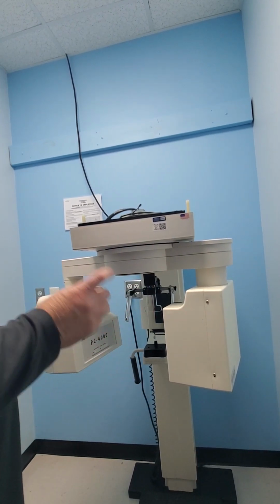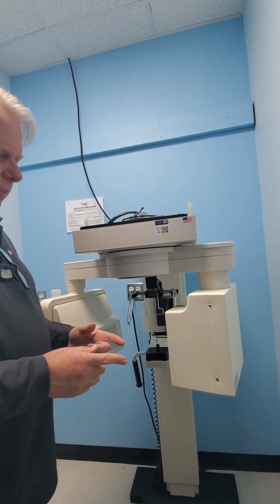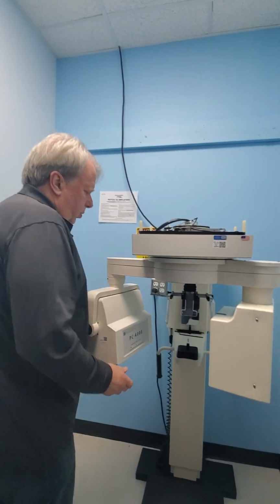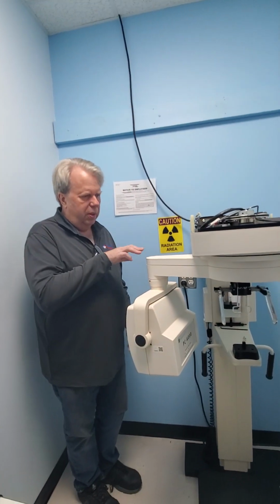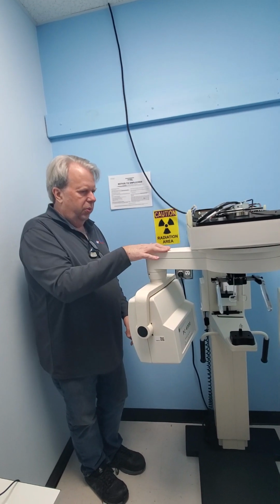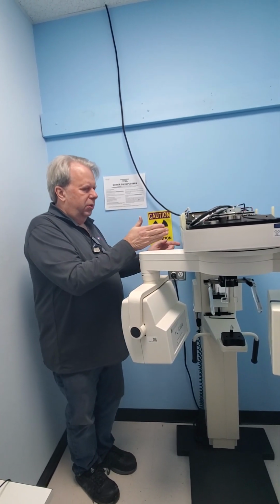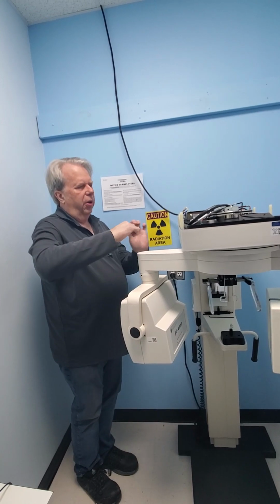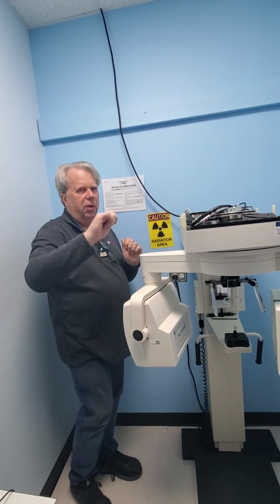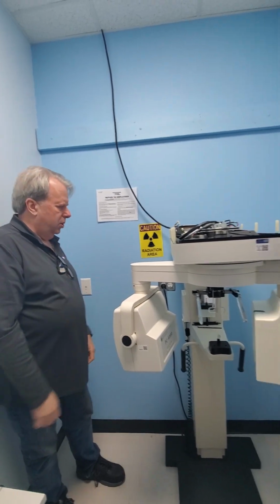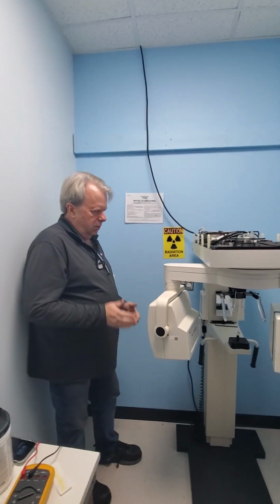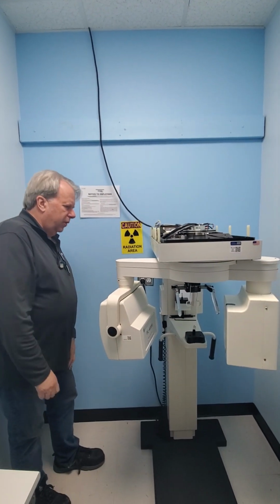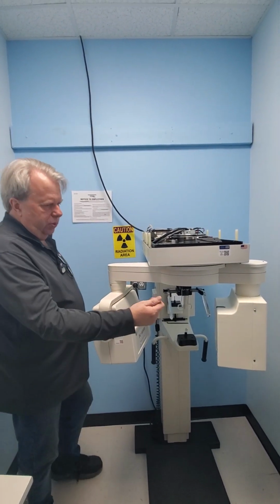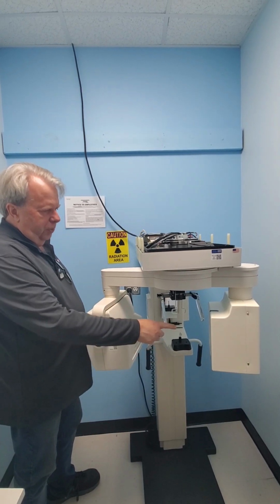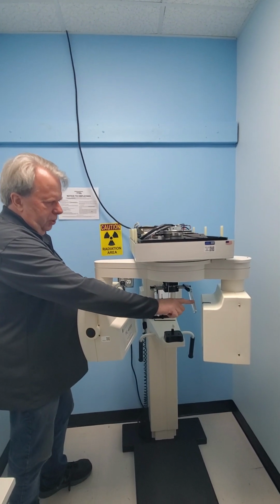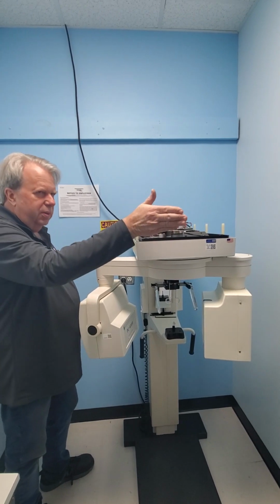Slotted? Yeah. It's also important not to get the beam skewed. In other words, you want the center of the beam to be right down the middle of the arm. You don't want it to be off this way and make your sensor come over to meet it. Are you going to get a really asymmetrical pan? You want to strike it at a right angle, as much at a right angle as possible. Dead center. They used to say when they had film drums, you took the film drum off and put a screen on the film drum shaft to make sure that you're hitting dead center.